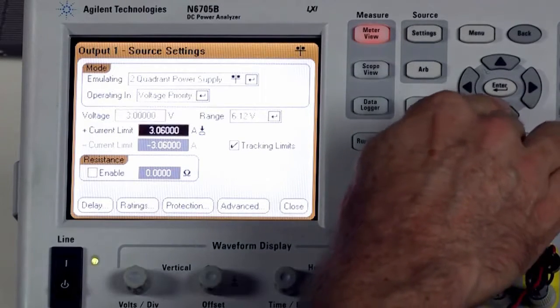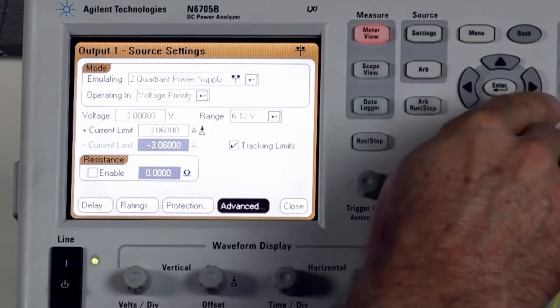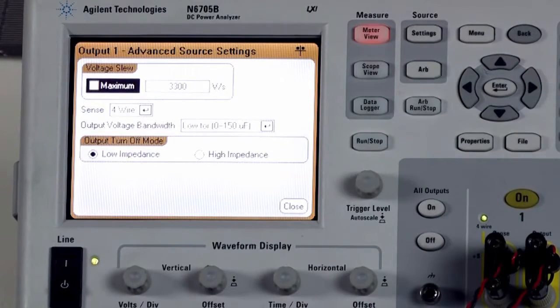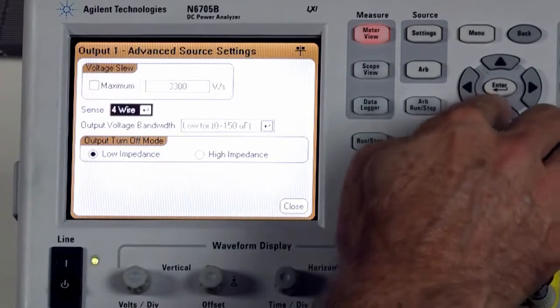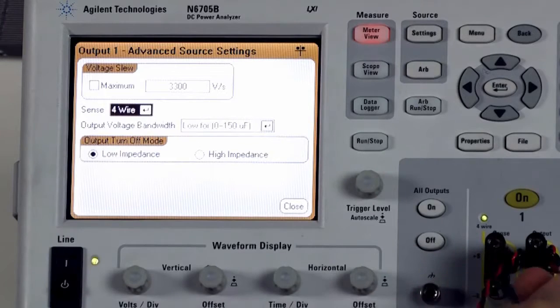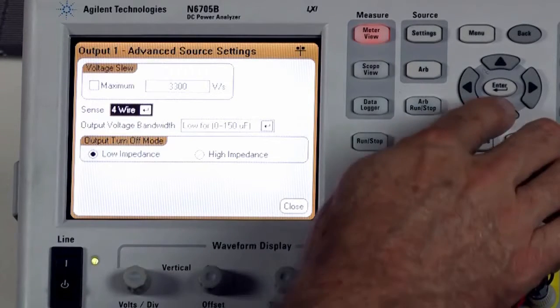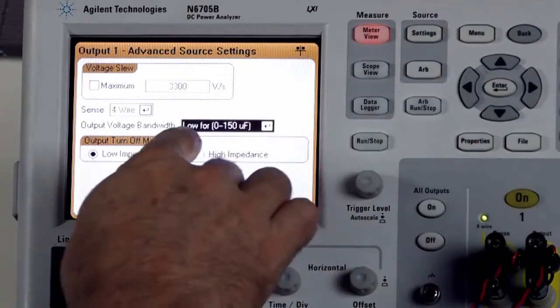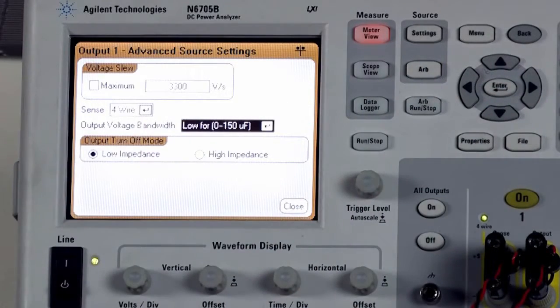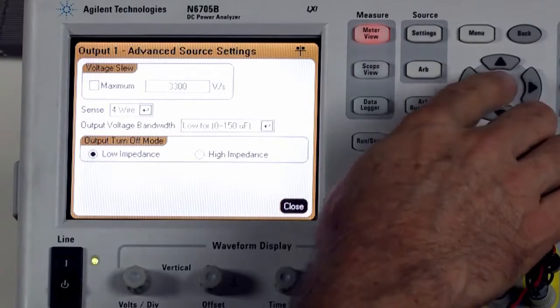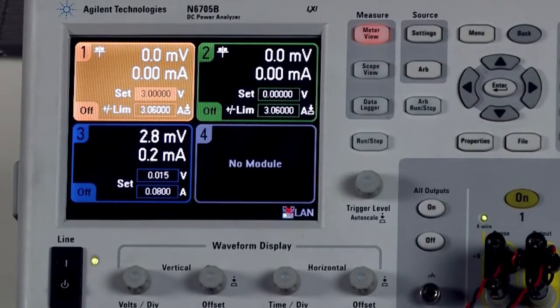There is one other place that I would like to make a selection, and that is in the advanced menu. So I toggle over there, and I go in and look at the advanced menu. I want to verify that we are using the 4-wire remote sense because we have it wired that way. And I also want to make sure that we have the output voltage bandwidth set to low. This basically will assume a larger capacitive load on your output and give you a slower response time for the output, which will minimize the opportunity for oscillations. So those look like they're set correctly. We'll close this, close that, and now we've got our SMU configured correctly.